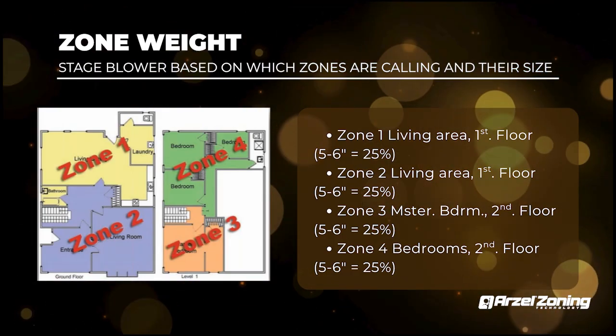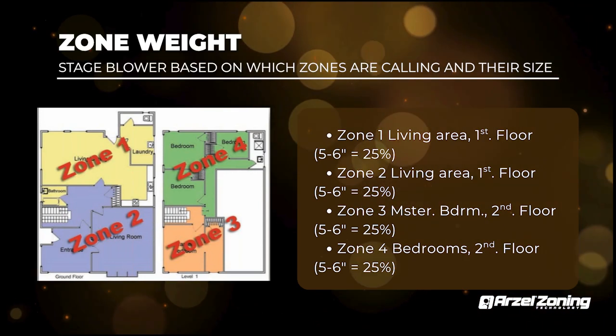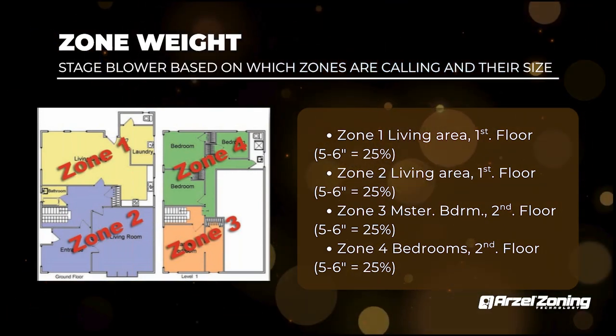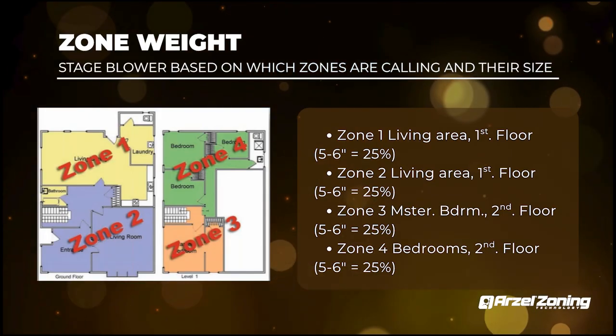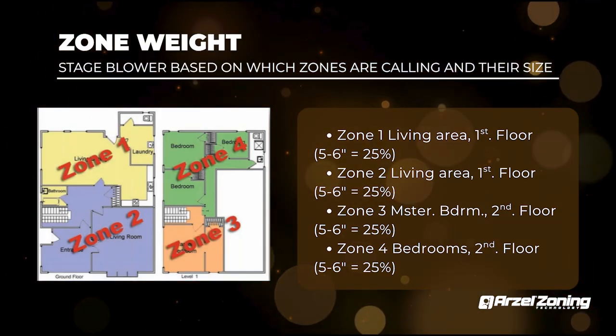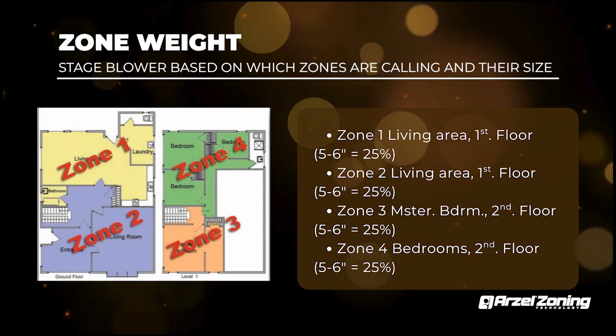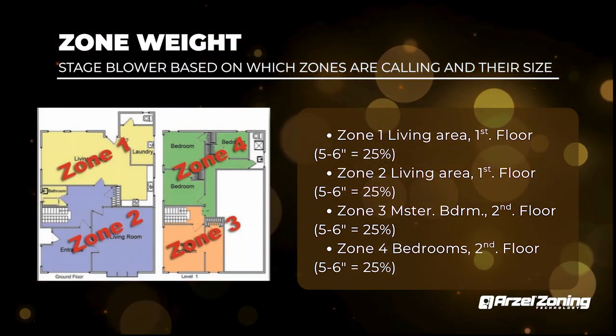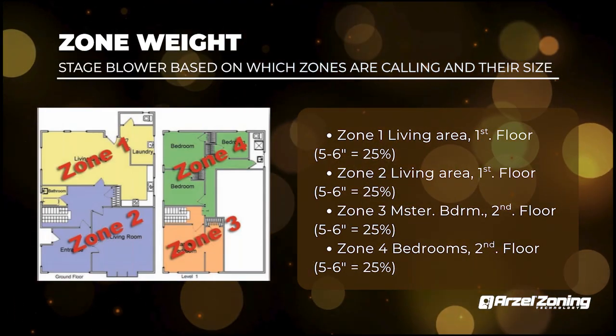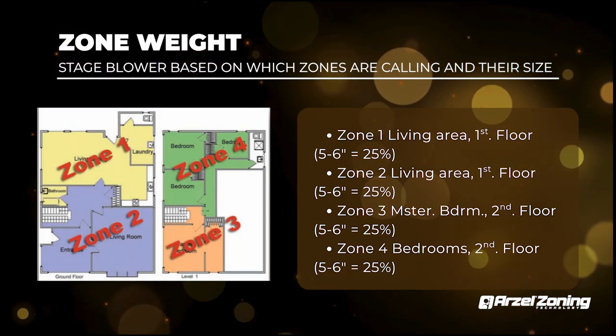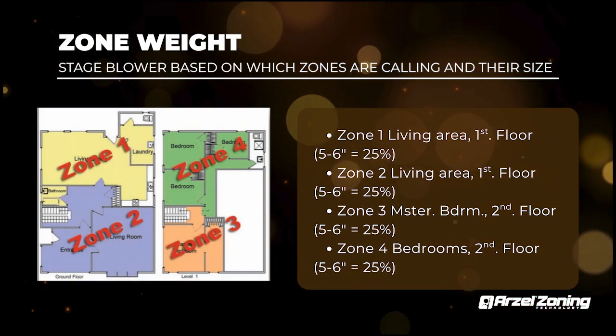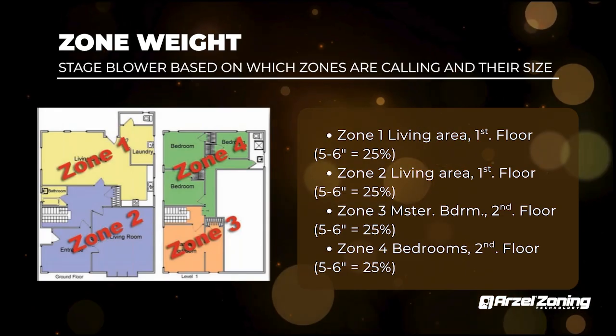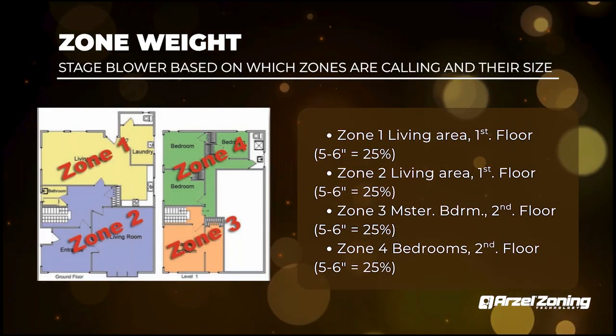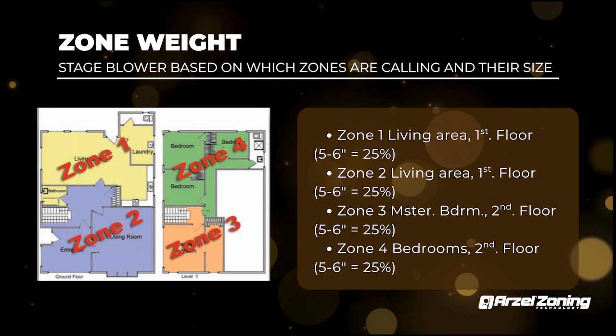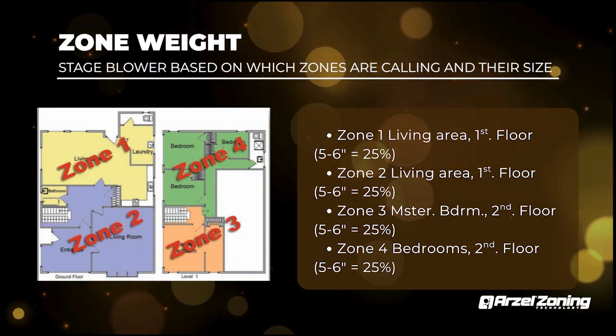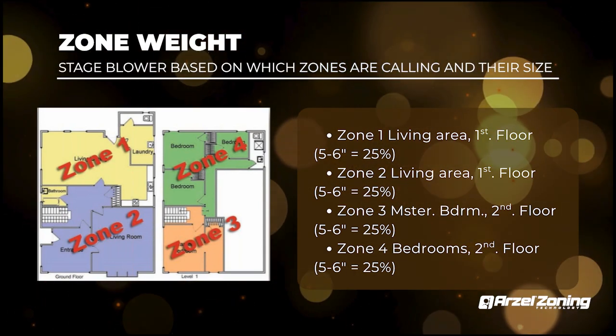And then there's going to be a setting in there called air handler stage threshold. Essentially what that is, how much of that percentage of ductwork do you want open in the system before you achieve a second stage on your output side of the panel. So if you guys in this case have all your zone weights set to 25, you have your air handler stage threshold set to 50. It would require any two of these zones to call before you were able to achieve a second stage blower operation. So it's a really nice feature. If you guys have any questions about this, give us a call. We can help you out on the phone as well. But that's really the easiest way to kind of communicate that to you guys.